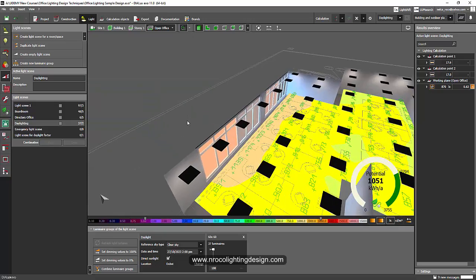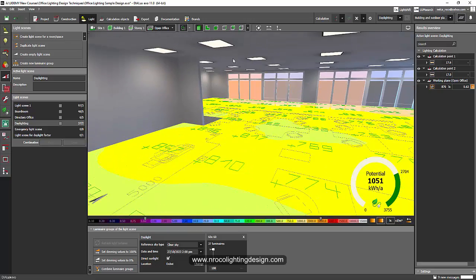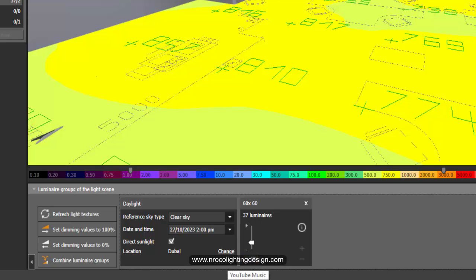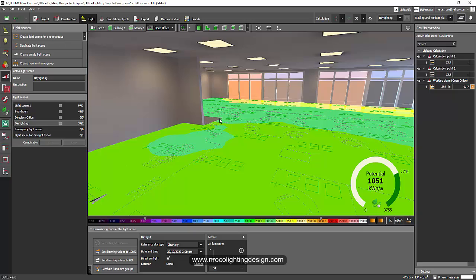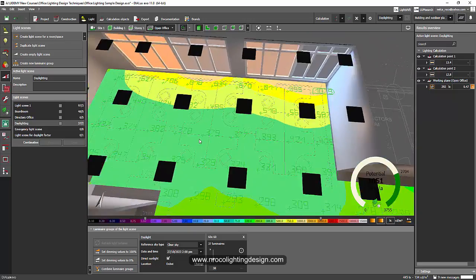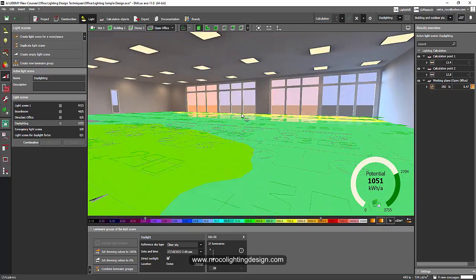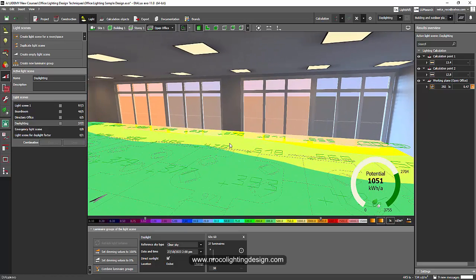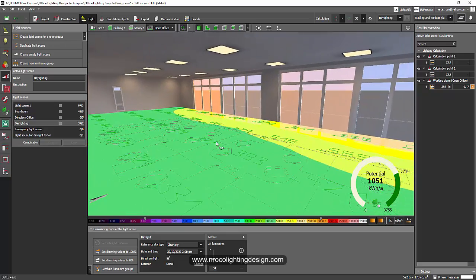And of course, you can easily think that this is too much and too bright for office lighting. So what we're going to do is reduce the level here to 30%. Let's see, and then refresh. And for this, you need a daylighting control to make sure that at 2 o'clock or higher light output from the sun going to that window, the daylighting control senses this daylight and adjusts the lumen output, it's going to dim down.